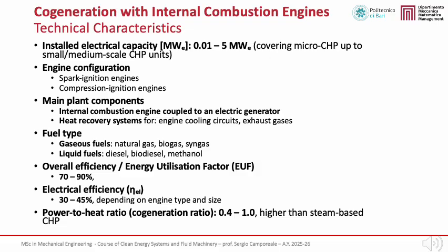Let us now look at the technical characteristics of ICE-based CHP plants. The installed electrical capacity typically ranges from 10 kilowatts up to about 5 megawatts, covering micro CHP as well as small and medium-scale CHP applications. Two main engine configurations are used: spark ignition engines and compression ignition engines, depending on fuel type, operating profile, and emission constraints. The core plant components consist of an internal combustion engine coupled to an electric generator, and heat recovery systems connected to the engine cooling circuits and exhaust gases.